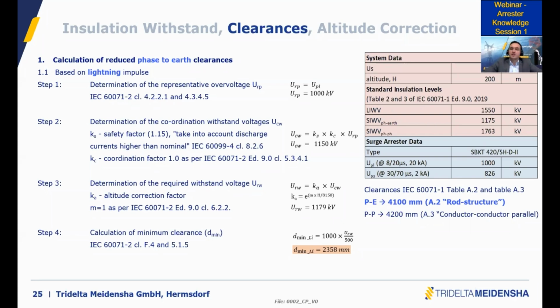You have two possibilities. You can increase the insulating base. It's also a possibility if you have this issue. But I would say the value is in the range of 2-3 meters, roughly, to make sure that the lightning impulse or the transient overvoltage goes to the ground. I mean, goes to the ground via the surge counter.